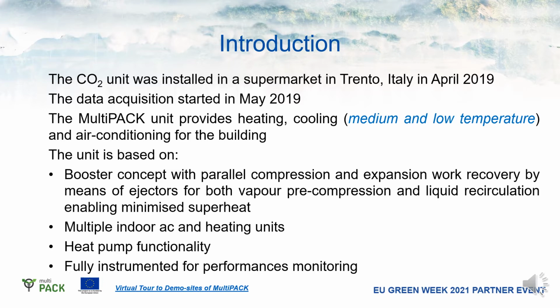It's based on a booster concept with parallel compression and expansion work recovery, applying a multi-ejector to enable a pre-compression of mainly vapor from the medium temperature to the auxiliary suction pressure. We also have in this unit multiple indoor air conditioning and heating units which are not connected to a centralized system via a water loop. They are connected directly with the CO2.